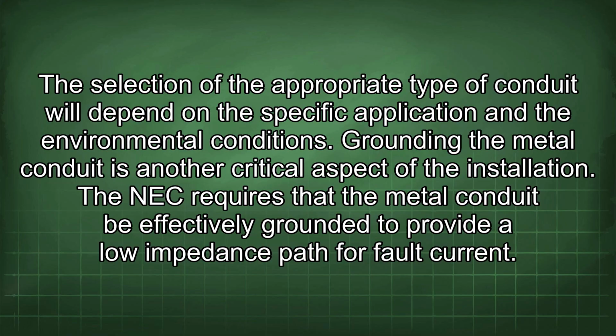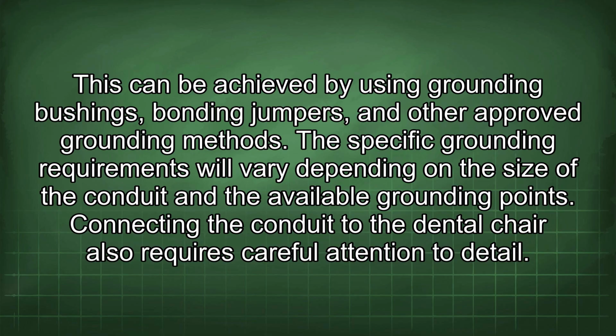Grounding the metal conduit is another critical aspect of the installation. The NEC requires that the metal conduit be effectively grounded to provide a low impedance path for fault current. This can be achieved by using grounding bushings, bonding jumpers, and other approved grounding methods. The specific grounding requirements will vary depending on the size of the conduit and the available grounding points.